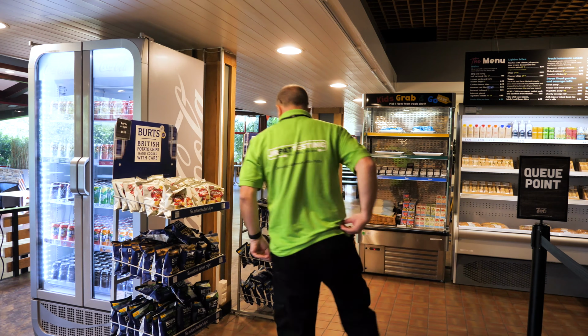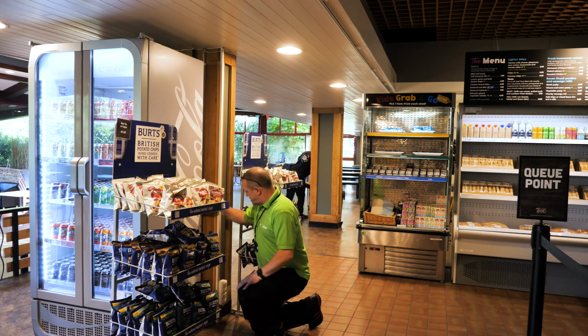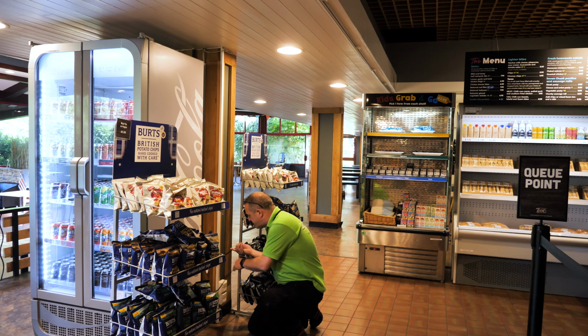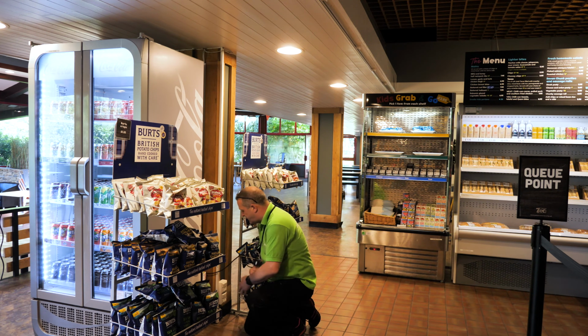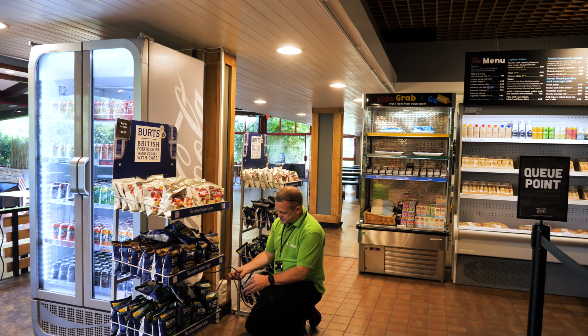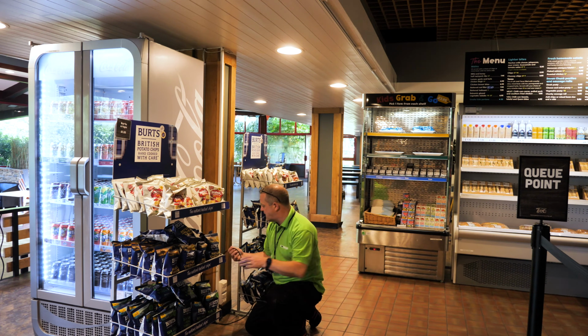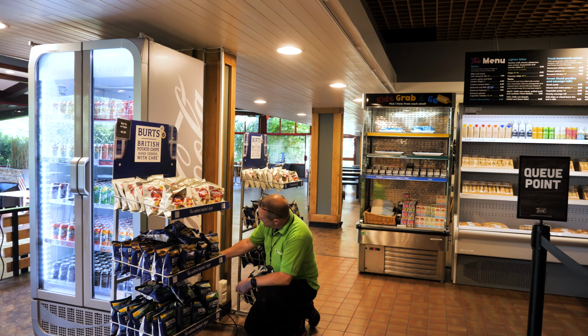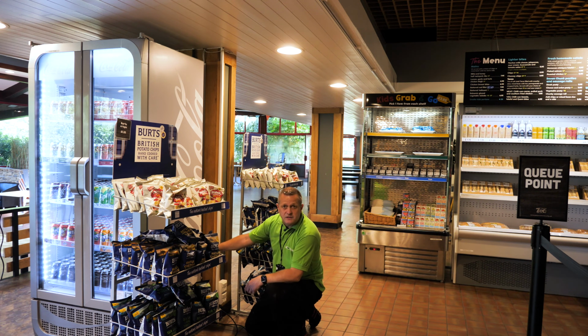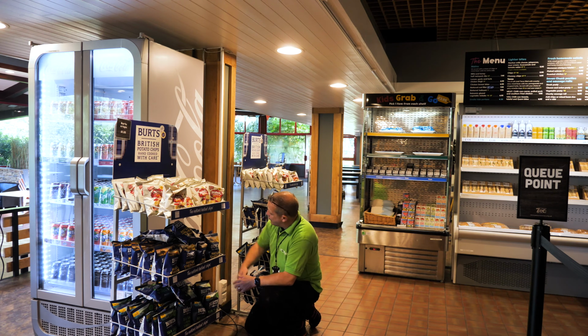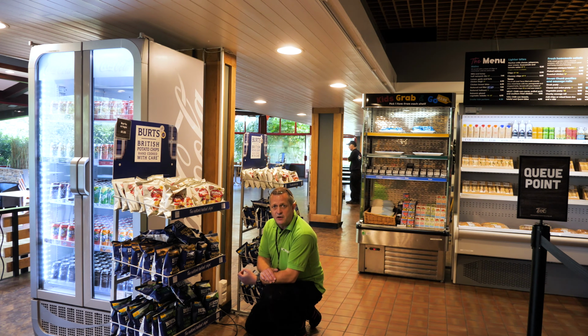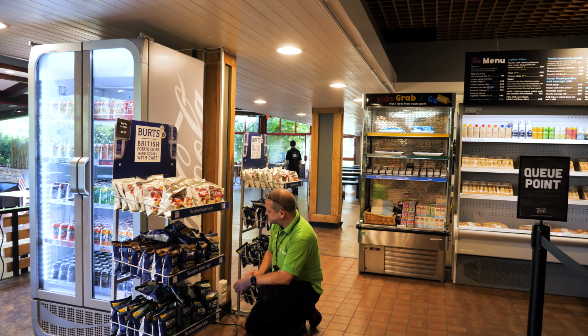So then it's trying to get access to the plug, so I can see it's down here. Whilst it's still in situ, I'm going to quickly have a look at the cable. No kinks, no tears or anything. And I'm going to quickly make sure that the socket is okay, making sure that it's not loose. If it is loose, then if we can, we will just quickly tighten it up. If that doesn't work, then we need to make sure that we report that to the responsible person so that they can get those repairs undertaken as quickly as possible.